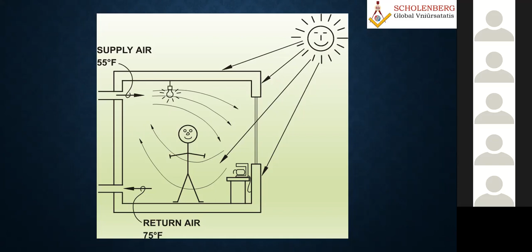So this is the same as what I have told. This is what I was telling you: why we have to go for a variable flow supply fan, variable flow exhaust and recirculation fan. I put the same thing in a different format, showing various rooms and various terminals. Why do we need to go for this type of VAV system? For that purpose only. Various different kinds of zones will be there, different kinds of air handling units. In some hospitals, we may have 100 air handling units and maybe 200 to 300 fan coil units. With chilled water fan coils, we also have 2-pipe or 4-pipe systems. This is just to recollect your knowledge on that.